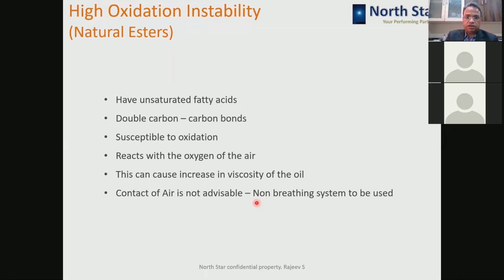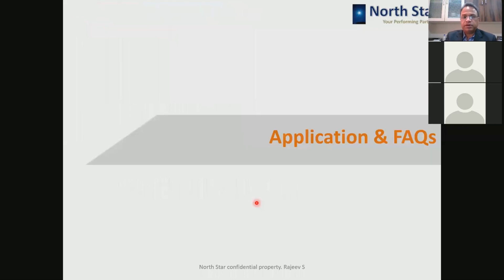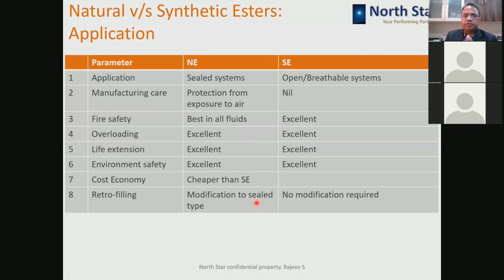Synthetic esters, because of their higher oxidation stability, are more robust materials, so they do not get affected because of exposure to the environment. That is the property which makes them a little bit more stable as far as the application is concerned. Now let us come to the application aspect and some frequently asked questions. Let us first compare natural and synthetic ester as far as application is concerned. As I said, you can use natural ester in sealed systems, and synthetic esters you can use in any open breathable system. It is as easy to use as mineral oil without much modification when you are doing retrofilling. You don't require any air cell, or a hermetically sealed transformer. In any normal breathable transformer, synthetic ester can be used.